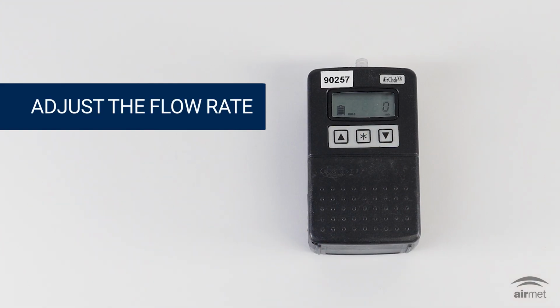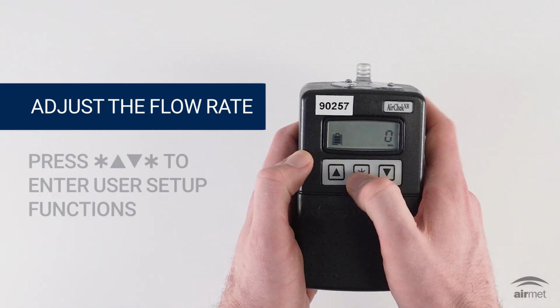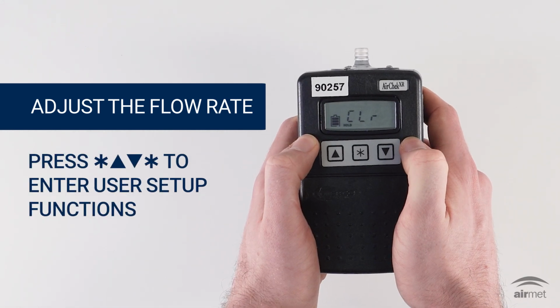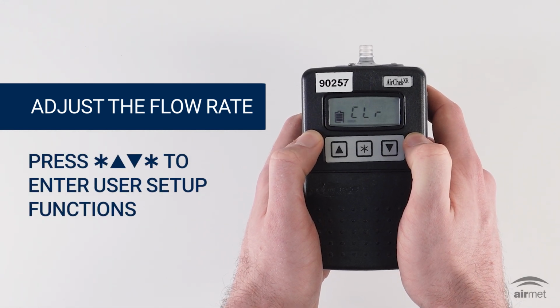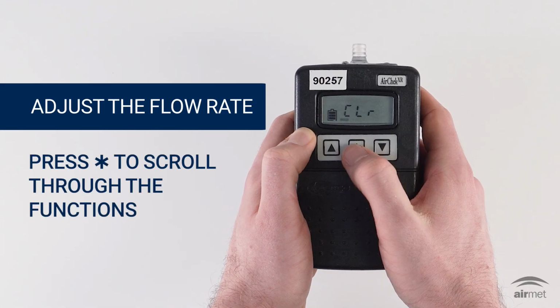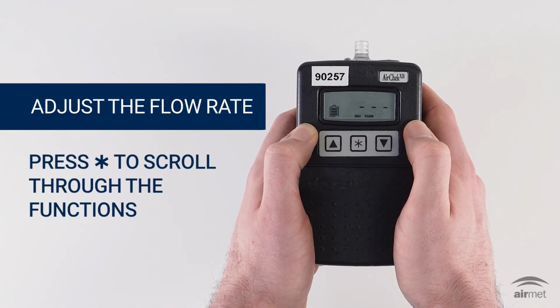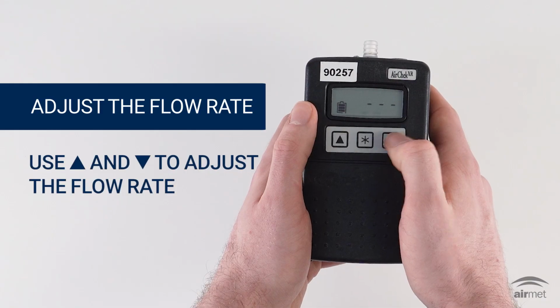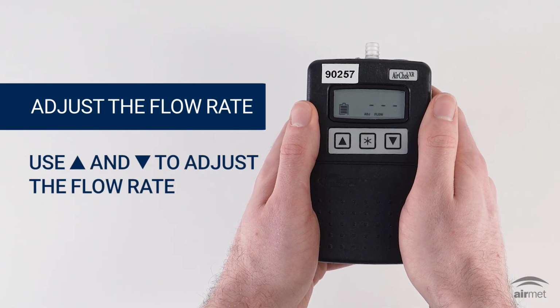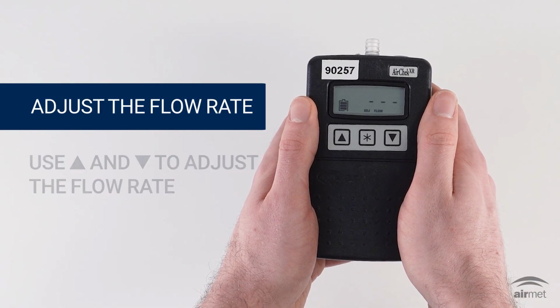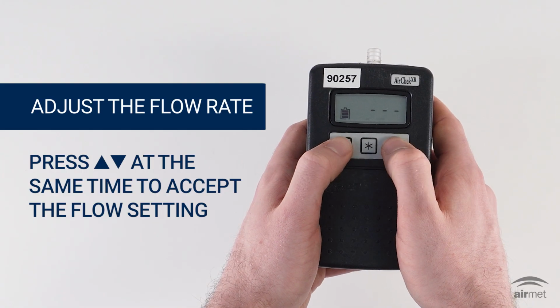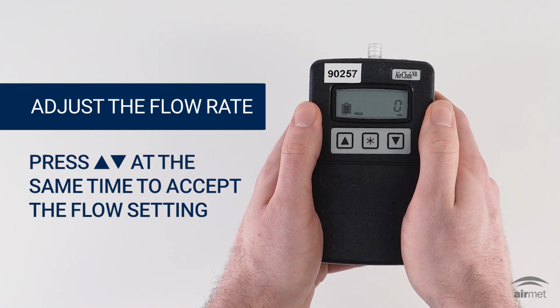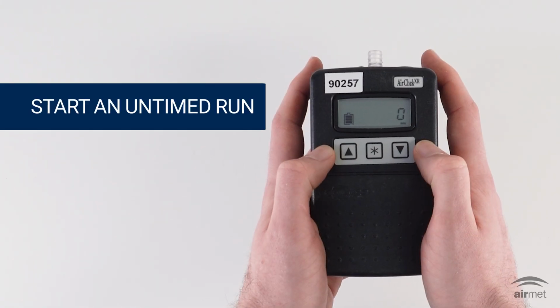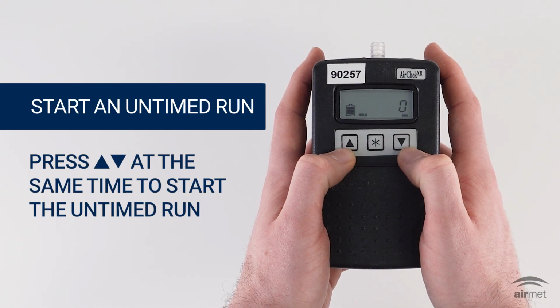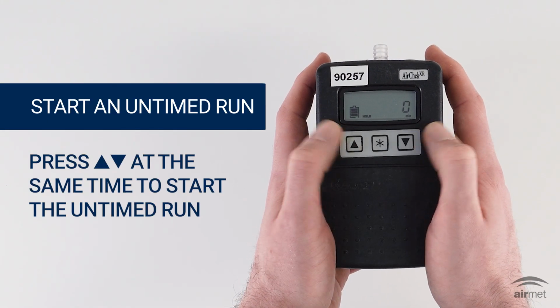To change the flow rate on your SKC XR5000, ensure the pump is in a non-running state. Press star, up, down, star on the keypad in sequence in order to enter the user setup functions. Use the star button to scroll through the display until it says adjust flow. Using the up or down arrows, adjust the flow rate and verify the new flow rate with a calibrator or flow meter. Pressing the up and down arrows together will accept the flow setting and exit the user setup. To start an untimed run, simply press the up and down arrow keys together.